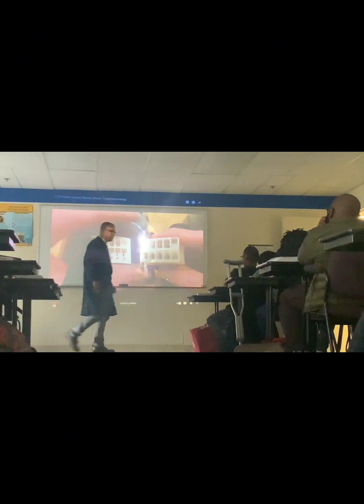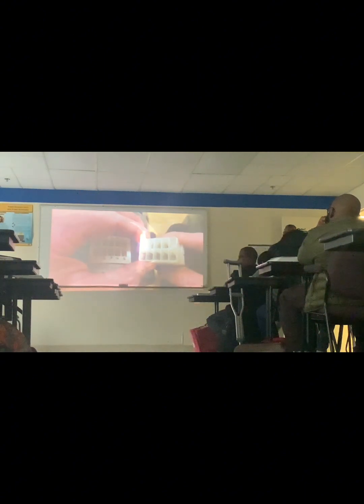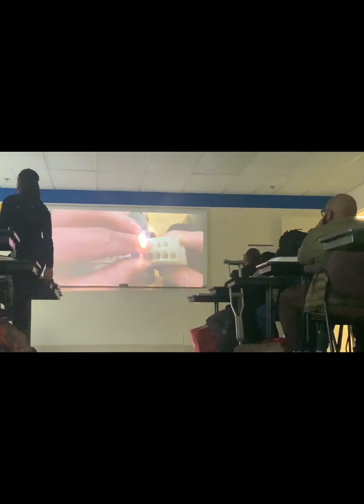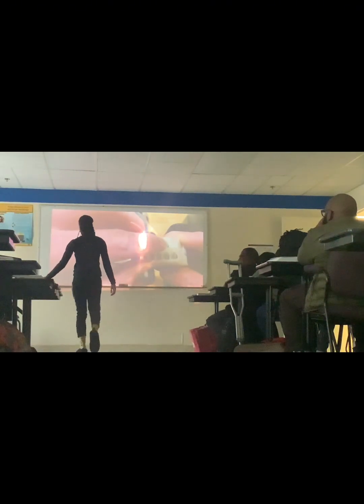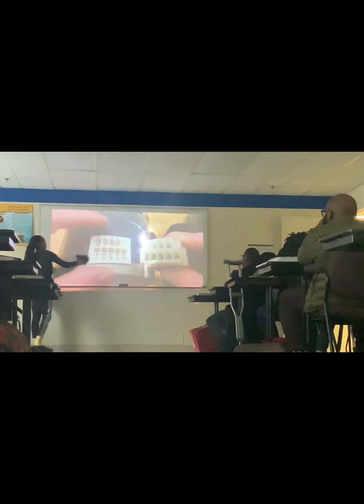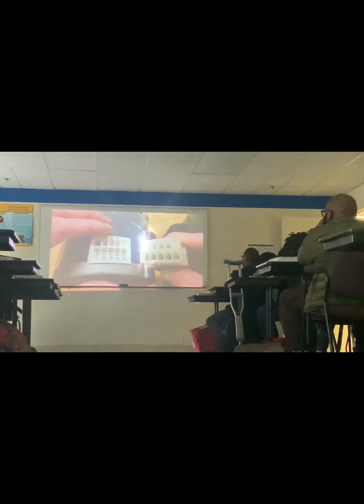This right here is the electrical connections for the X13 blower motor, and this one's for the Broad Ocean blower motor. You can see this tab right here is larger than these three. These three small ones are your high voltage taps, and they're going to be hot all the time. The blower motor won't turn on until it gets its 24-volt signal wires, so you have your 24-volt hot wires down here for your speeds, and this one right here is your common for the 24 volts. So this is not part of your high voltage taps - this is your low voltage common.